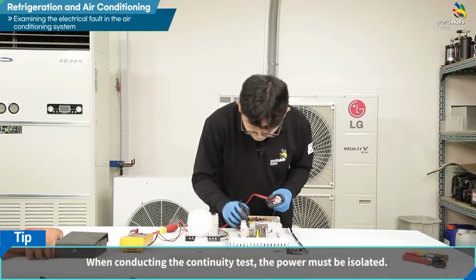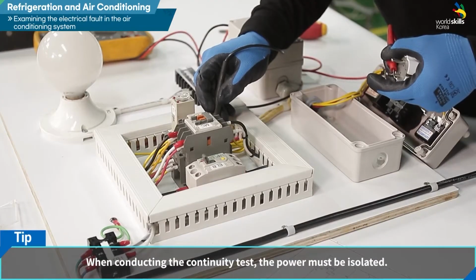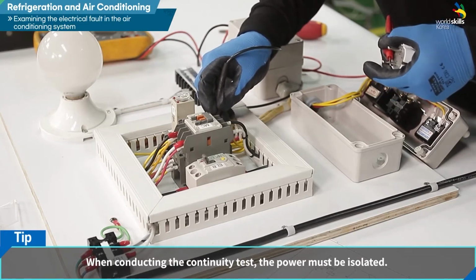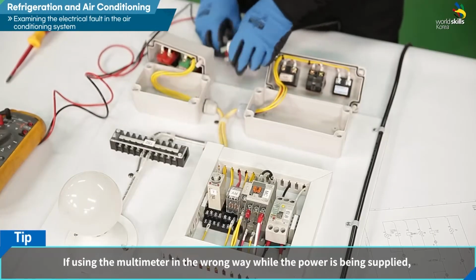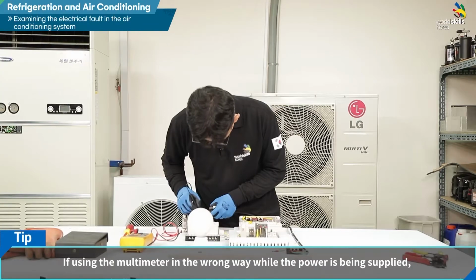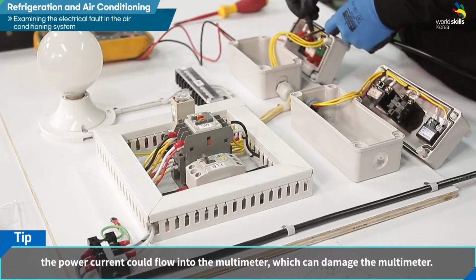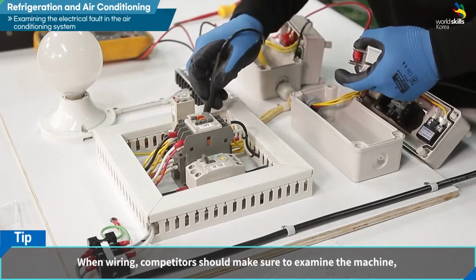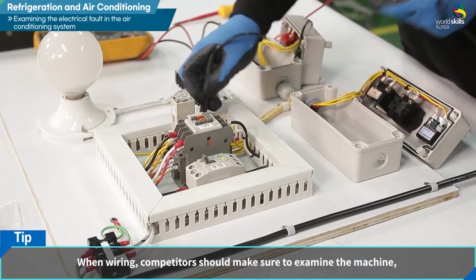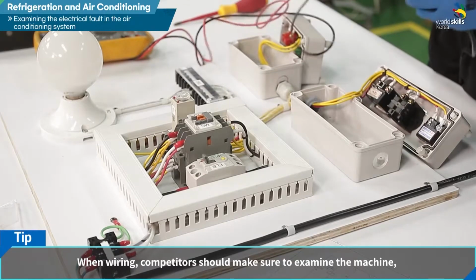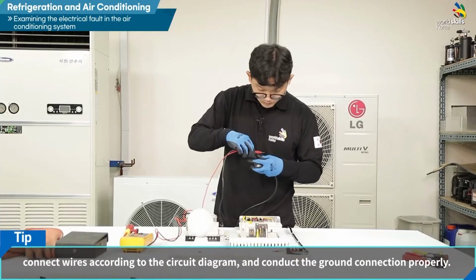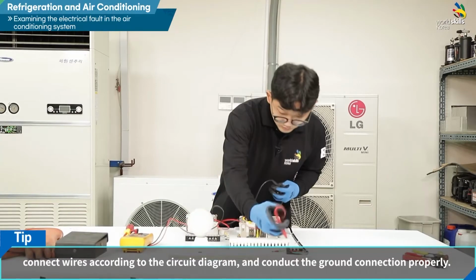When conducting the continuity test, the power must be isolated. If using the multimeter in the wrong way when the power is being supplied, the power current could flow into the multimeter, which can damage the multimeter. During wiring work, you should make sure to examine the machine, connect wires according to the circuit diagram, and conduct the ground connection properly.